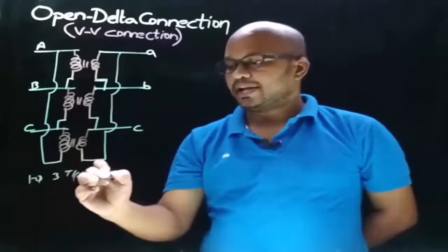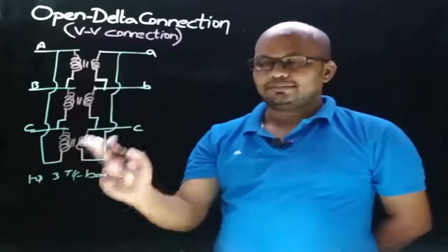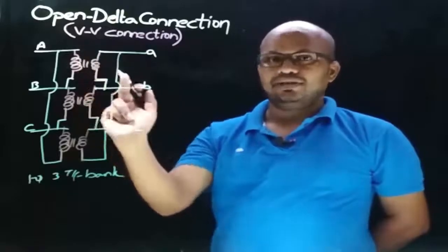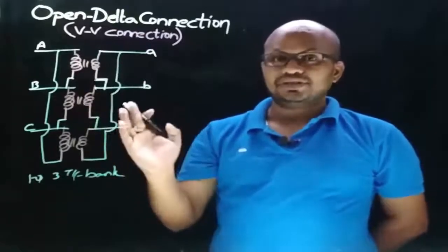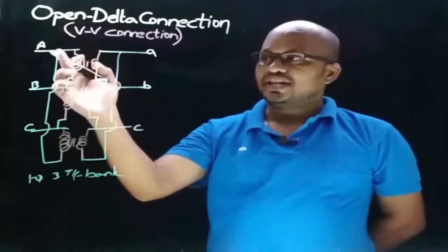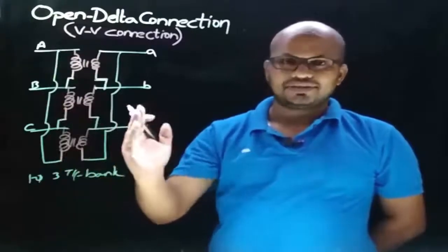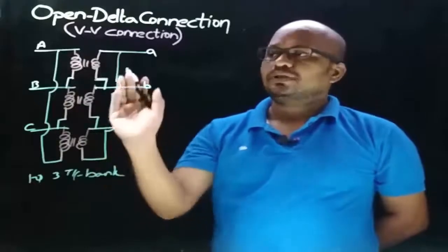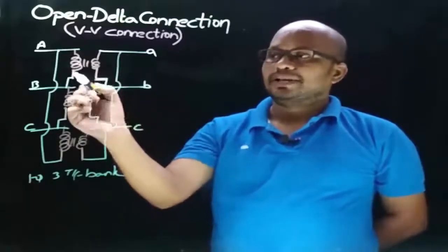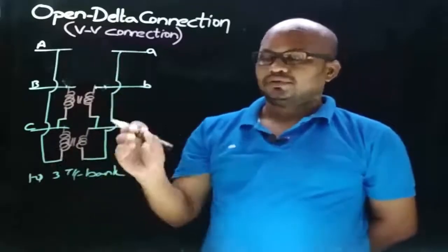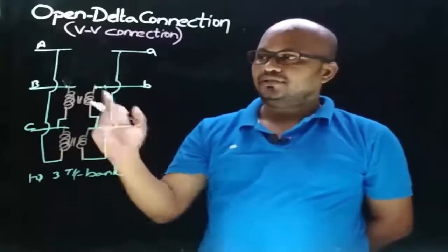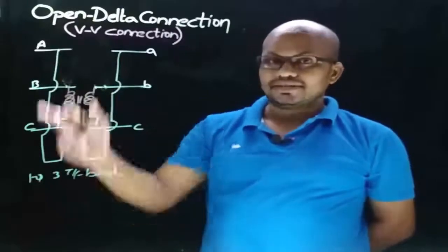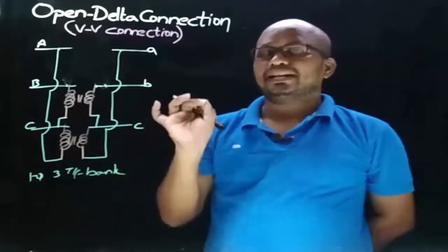This is how the delta-delta connection is obtained for a single-phase three-transformer bank. Open delta connection means if one of the transformers in this bank gets failed, then the resultant connection is called open delta connection. Let's consider transformer one got failed. We are transferring three-phase power with phase sequence ABC from the primary side to the secondary side. After removing transformer one from this bank, we can still maintain the three-phase supply with the same phase sequence ABC.